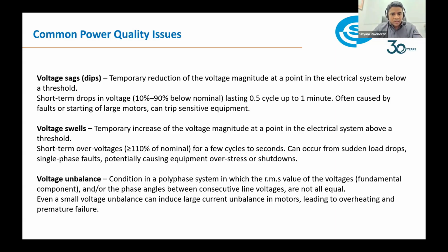So how many events are being recorded as voltage sag? How does it impact the customer? That is a secondary point. Voltage swell, again, is the same with a tolerance. Here, it is a temporary increase of a voltage magnitude at a point in an electrical system above a threshold. And what is the threshold? Which is more than 10%. So we can put it this way: if there is a dip, you call it a voltage dip, and if it is increasing, we call it a voltage swell.